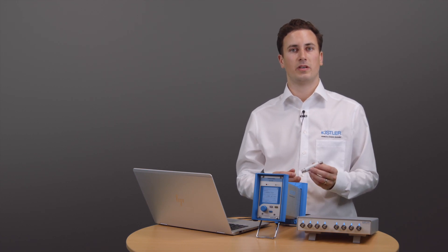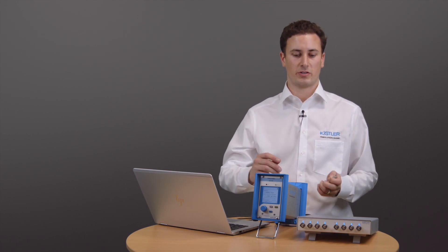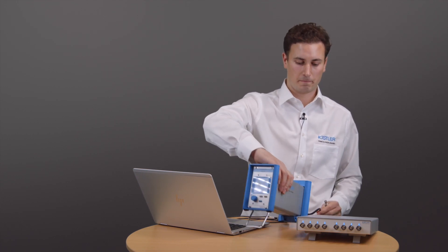I will start out with the reference capacitor. It is best practice to connect it as close as possible to the input of the charge amplifier.